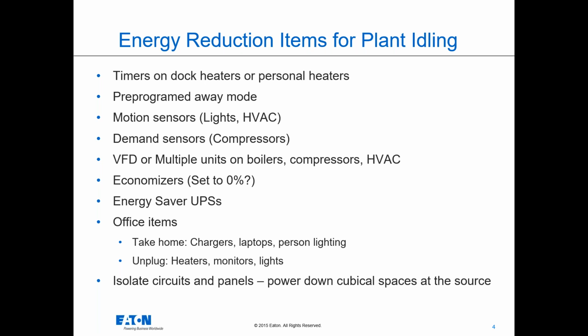If there's nobody in the building, you can look at your economizers and consider reducing that down. There's usually a set point based on your particular facility and how much fresh air you need to bring in to maintain good climate. But if there's no one inside the building, just like locking all the doors, you might be able to set those economizers down to zero and just recirculate your air the entire time. Really based on your situation though - if you have chemicals or off-gassing or anything like that, you wouldn't necessarily want to make your facility closed loop like that.